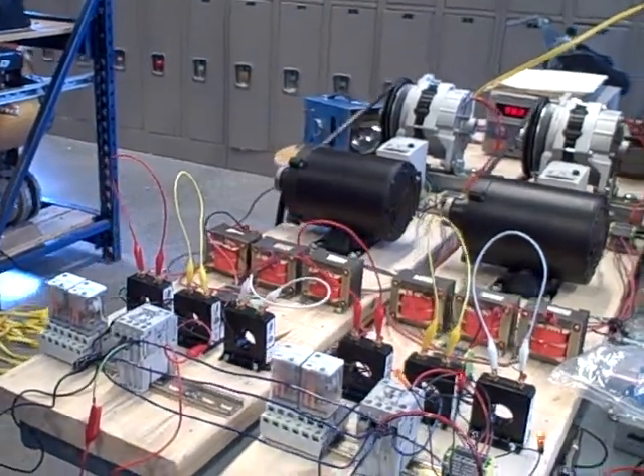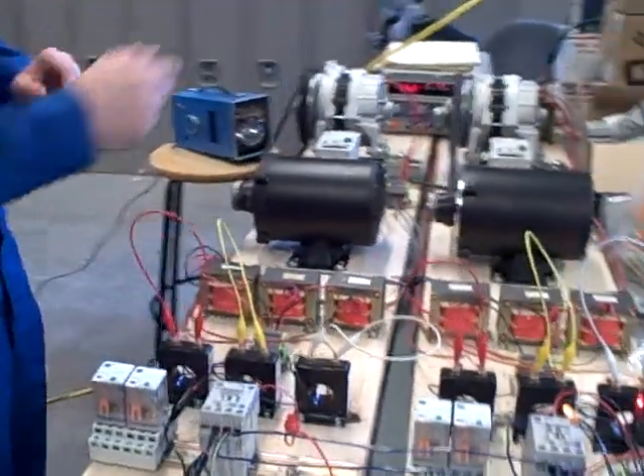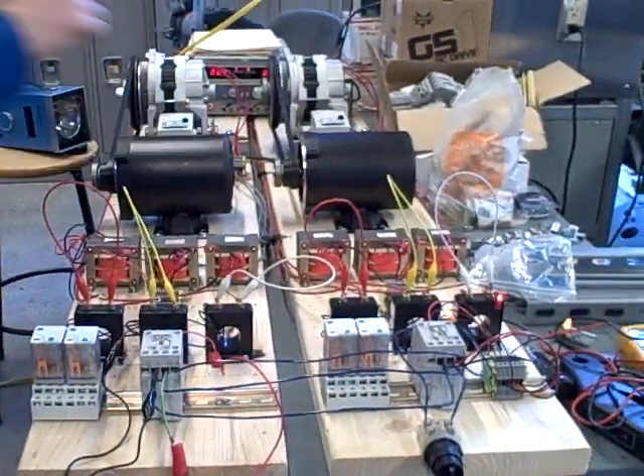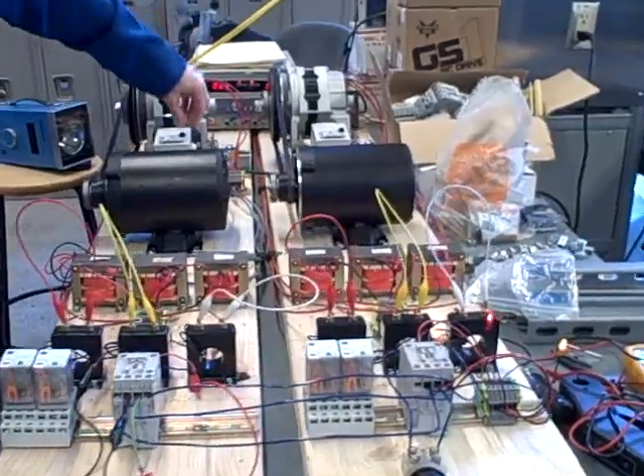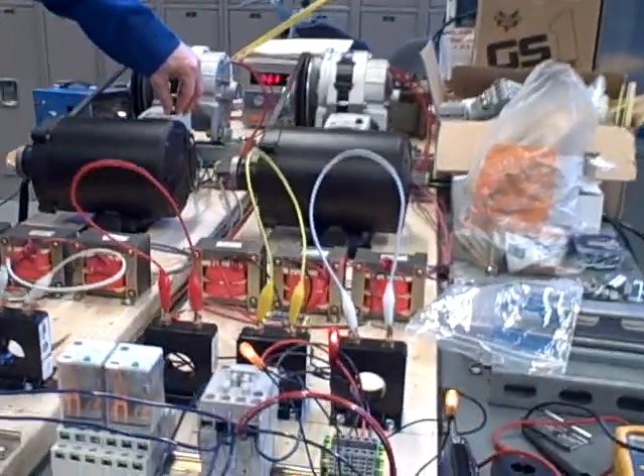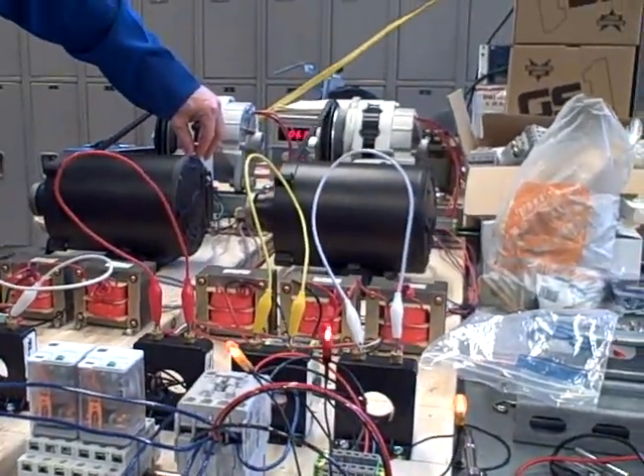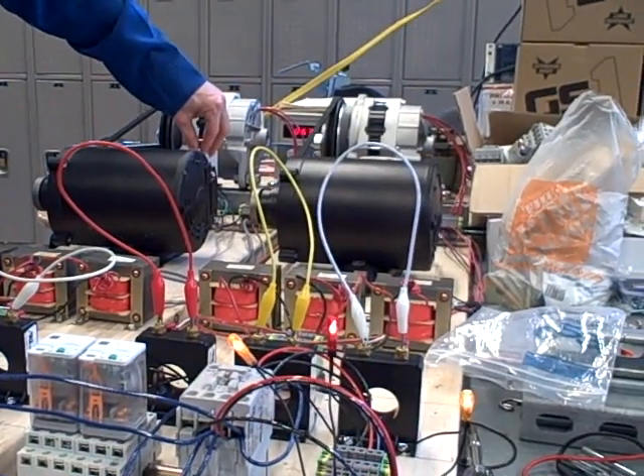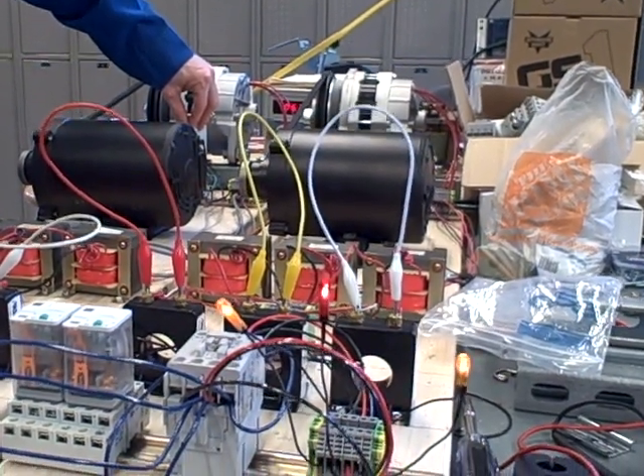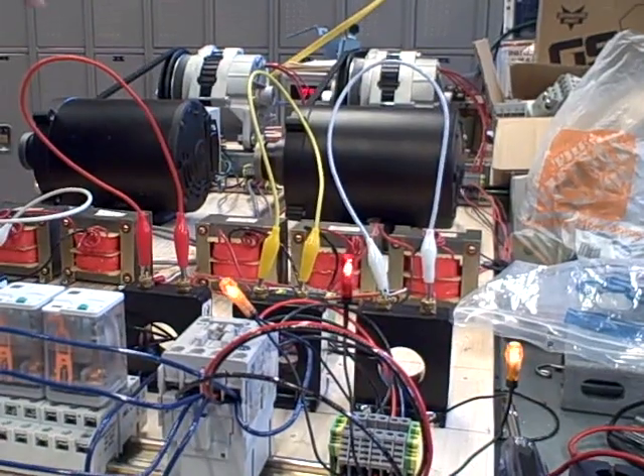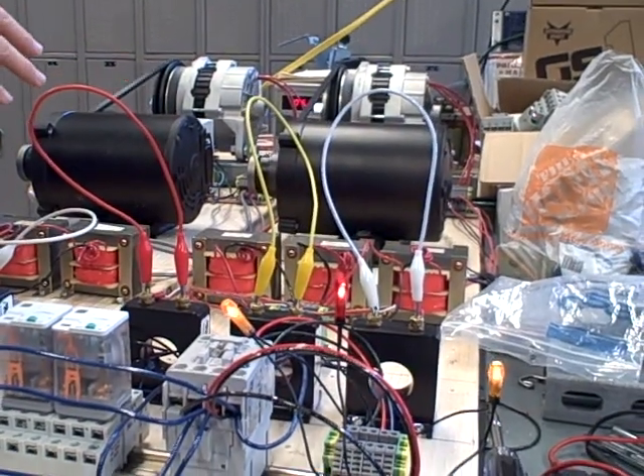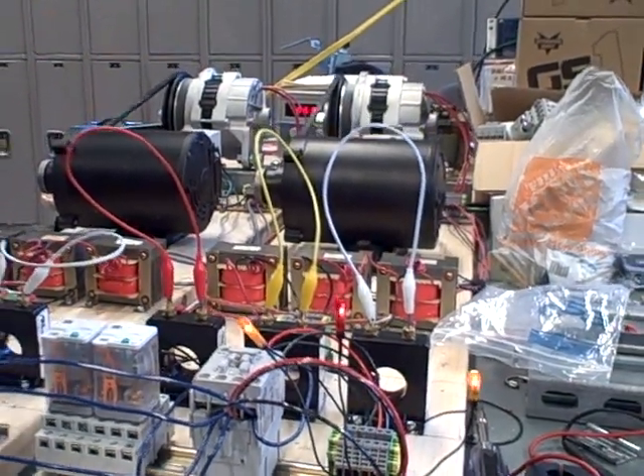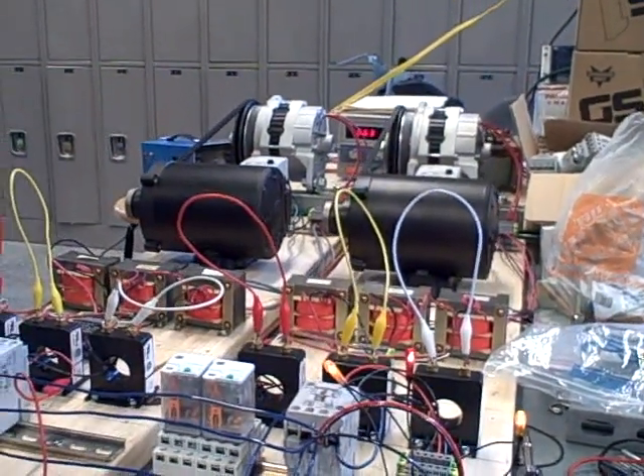So what I'm going to do is change the speed of this one generator over here, and you will see the blinking rate change. So right now I'm going too slow. If I go slower yet, you'll see the lights blink faster. If I go slower yet, it blinks even faster. The slower this generator goes in comparison with the other one, the faster they roll in and out of phase with each other.